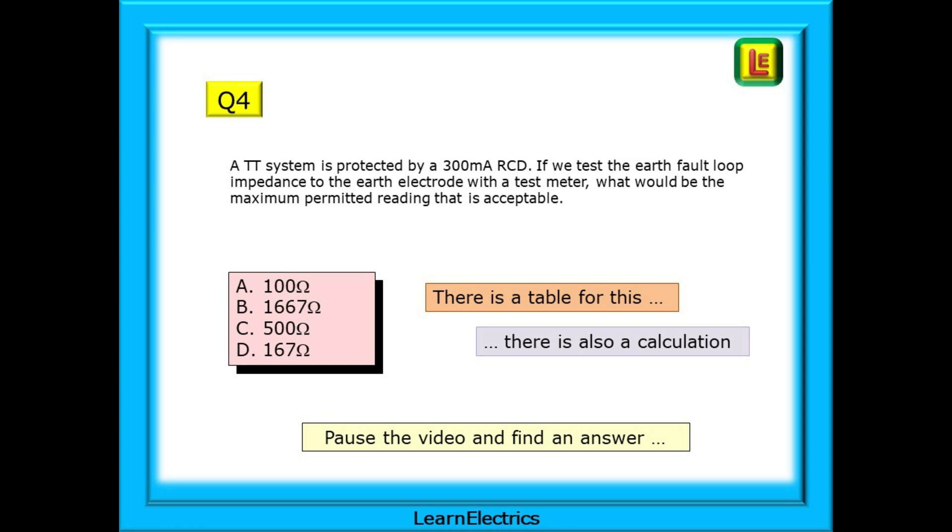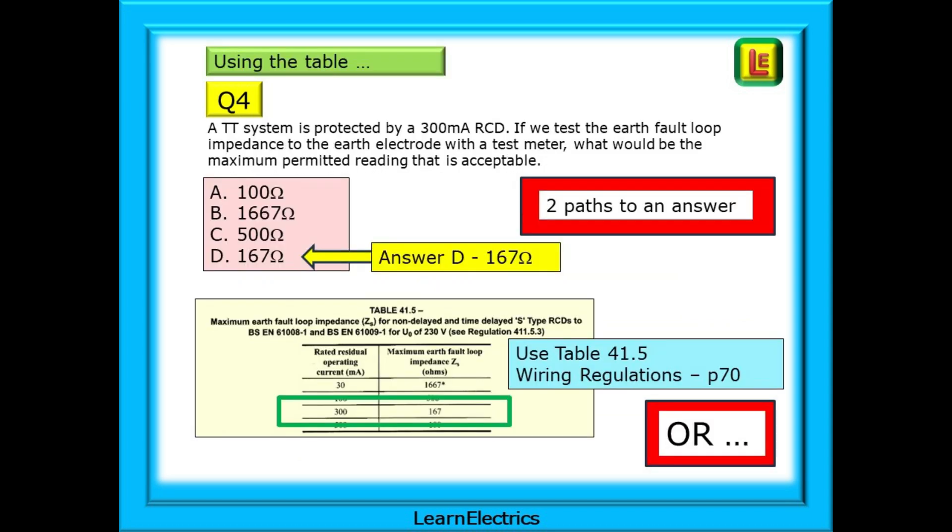Pause the video and find an answer. If we wish to use the table, go to page 70 of the Brown Wiring Regs book and find table 41.5. It's an easy task now to look at the table, find 300mA and read off the answer 167 ohms. We should choose answer D.